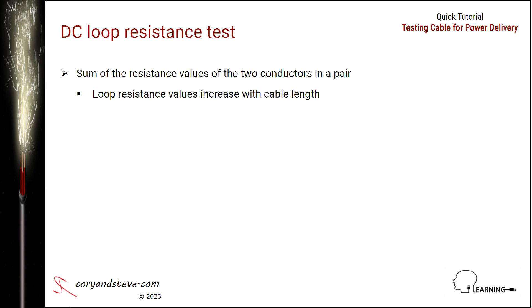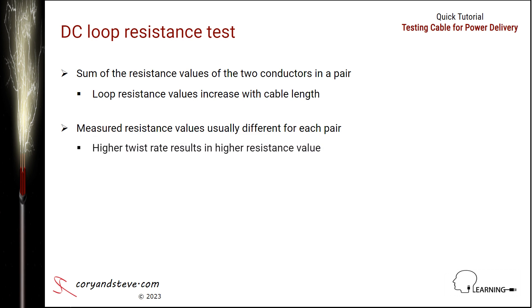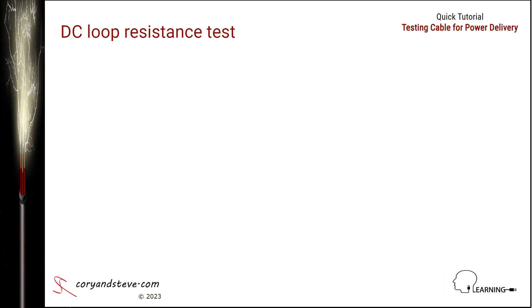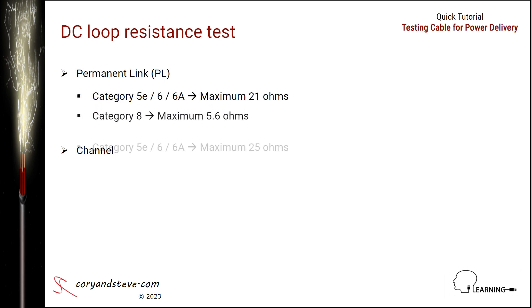Since the four pairs in a cable are twisted at different rates, the measured loop resistance values will usually be slightly different for each pair, with a higher twist rate resulting in a higher resistance value. However, a significantly higher loop resistance value for any one pair may be an indicator of a faulty termination of that pair on a connector located in the link or channel.